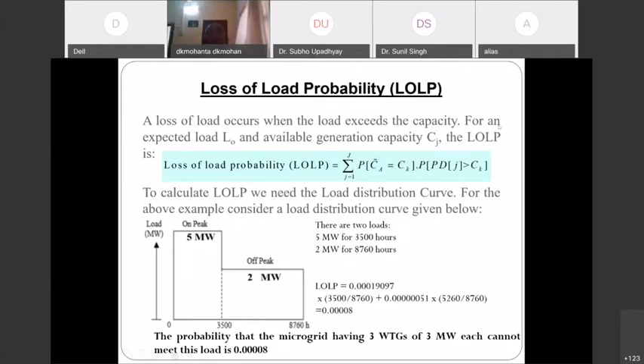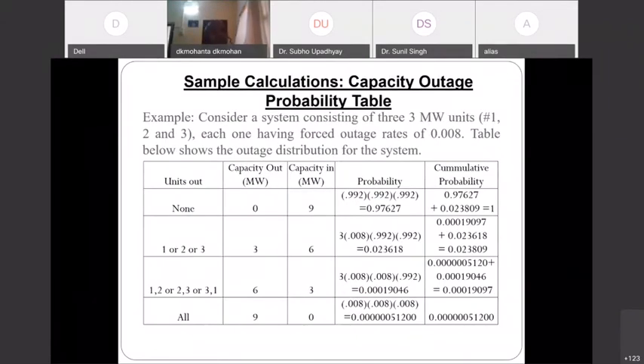How? The loss of load occurs when the load exceeds the capacity, for an expected load L0 and the available generation Cj. The loss of load probability is the probability that your generation is less than the load. For example, here there are 2 load levels: 5 megawatt for 3500 hours and 2 megawatt for the remaining hours of the 8760. So what is my loss of load probability? My load here is 5 megawatt, so any outage which leaves capacity below 5 megawatt will lead to loss of load. When 9 megawatt is available and load is 5 megawatt, naturally there will be no loss of load. When capacity available is 6 megawatt and load is 5 megawatt, we will not have any loss of load. So whenever generation falls to 3 megawatt, that time we will have loss of load.